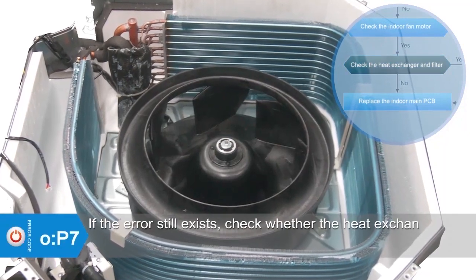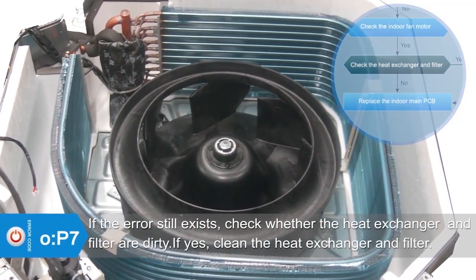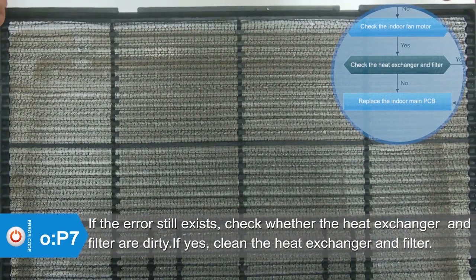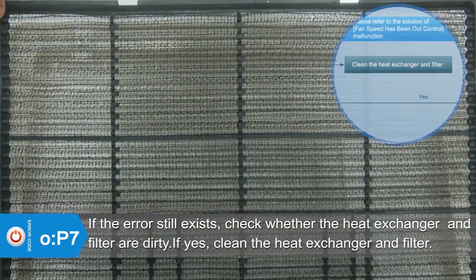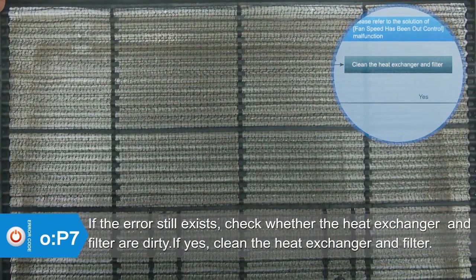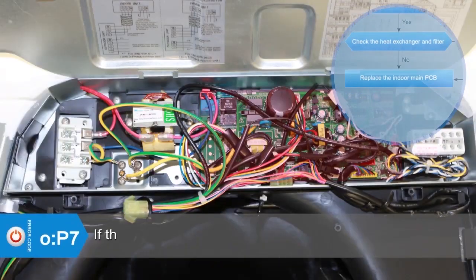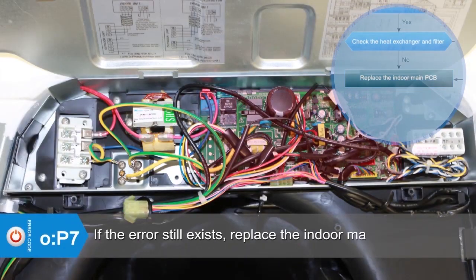If the error still exists, check whether the heat exchangers and filters are dirty. If yes, clean the heat exchangers and filters. If the error still exists, replace the indoor main PCB.